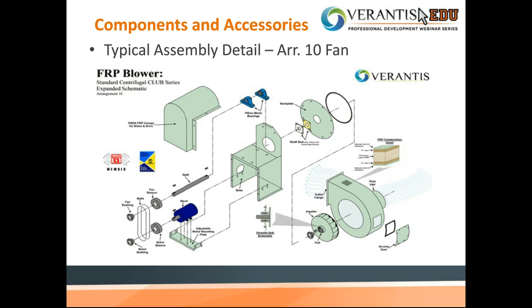These are the sheaves. You have a motor sheave, and above that you have the shaft sheave. Those get held together by a bushing, and then the belt goes around it, and that's how you actually turn the impeller. All of that gets mounted to the base. The inboard and outboard bearings get put on the shaft. This particular arrangement has a canopy, an OSHA canopy, which covers all the rotating pieces of equipment: the shaft, the pulley, the belt, all that good stuff.